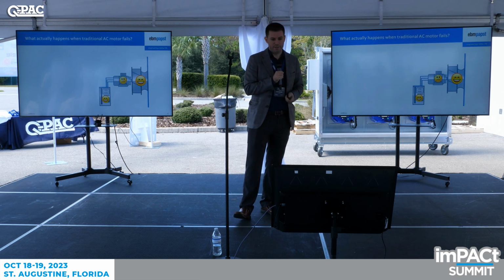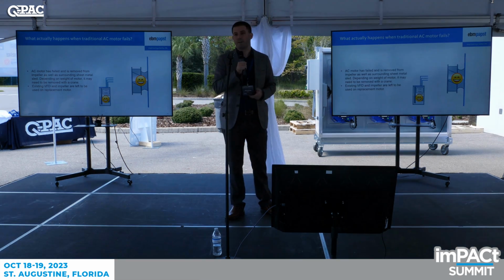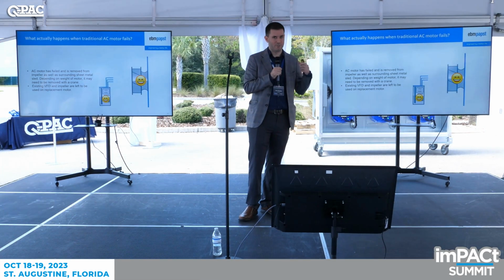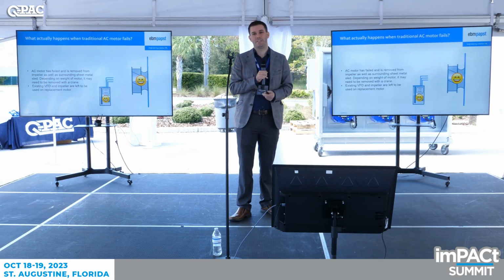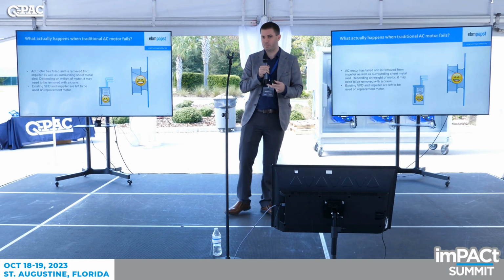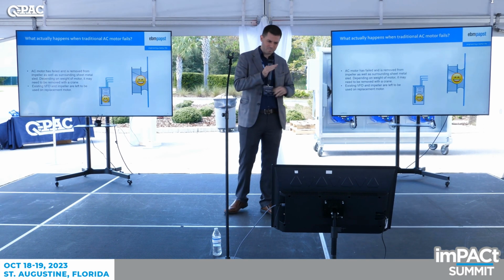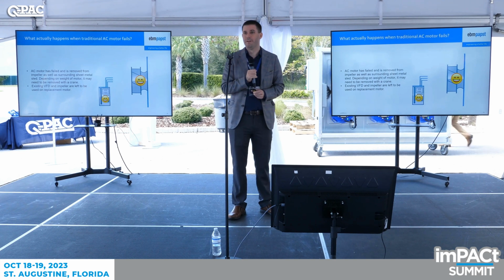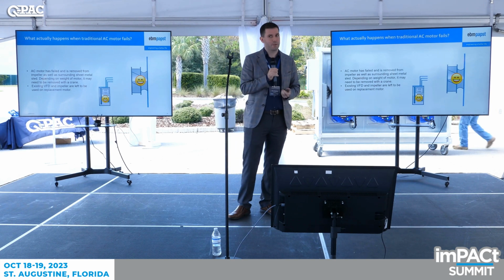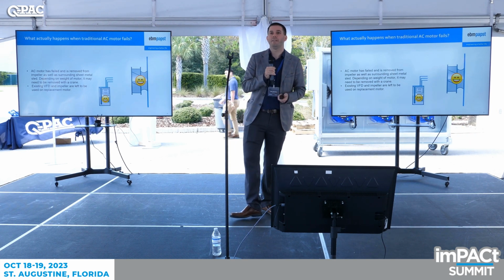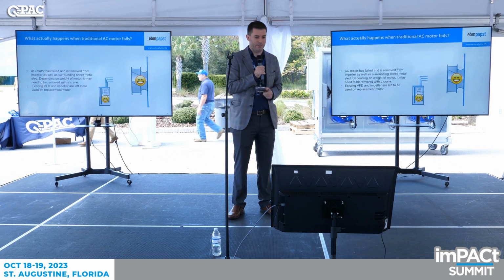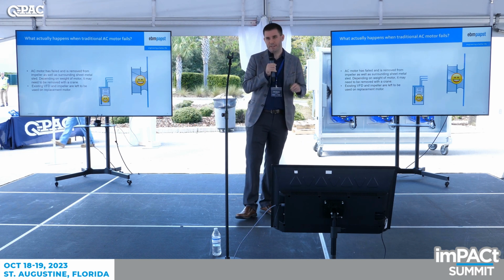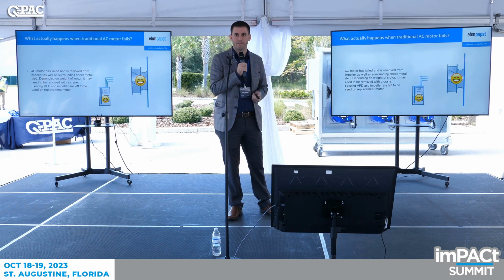The reality, though, is the motor fails. You remove the motor. Because lots of times, as we mentioned before, these could be big motors. You'd have to take this apart piece by piece to get it through that small door that we were talking about. The building might have been built around the air handler that this motor's in. So it could be a real challenge to get this motor out. You might need a crane, a little jib crane in the unit. And then the existing VFD and impeller are still going to be left there.